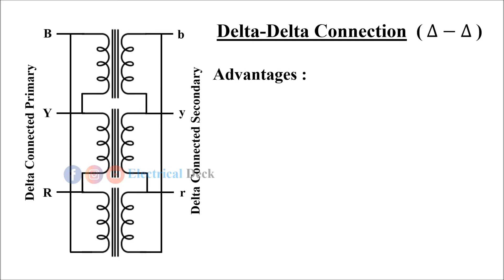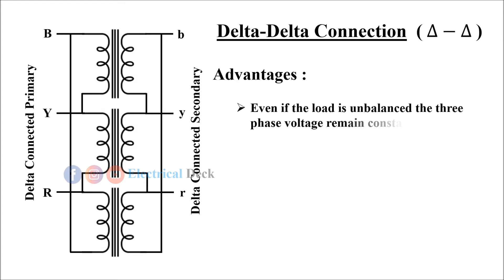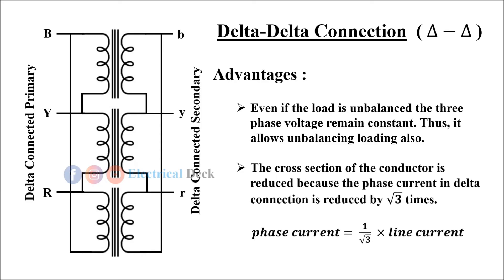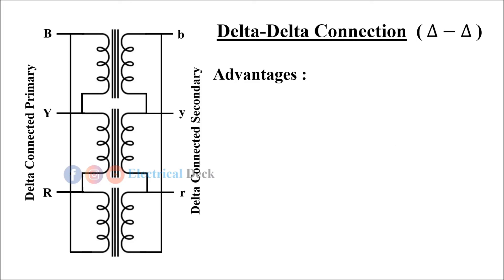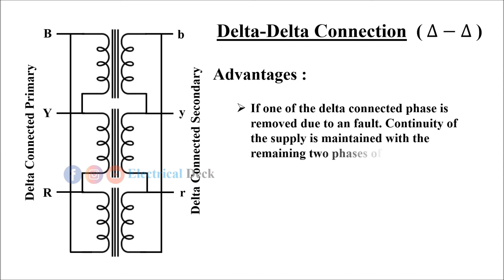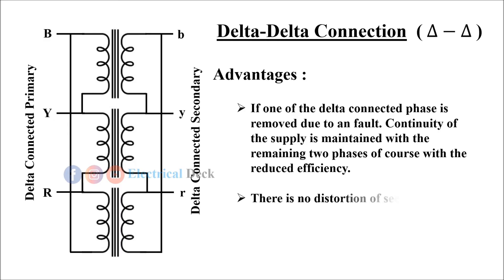The advantages of using delta-to-delta connection are: even if the load is unbalanced, the three-phase voltages remain constant, thus it allows unbalanced loading also. The cross-section of the conductor is reduced because the phase current in delta connection is reduced by root three times. If one of the delta-connected phases is removed due to a fault, continuity of the supply is maintained with the remaining two phases, with reduced efficiency.